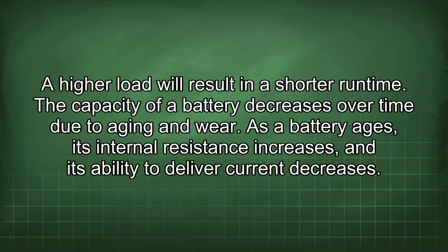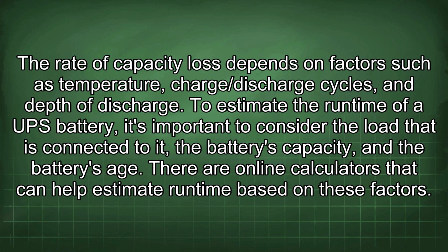The capacity of a battery decreases over time due to aging and wear. As a battery ages, its internal resistance increases, and its ability to deliver current decreases. The rate of capacity loss depends on factors such as temperature, charge/discharge cycles, and depth of discharge.